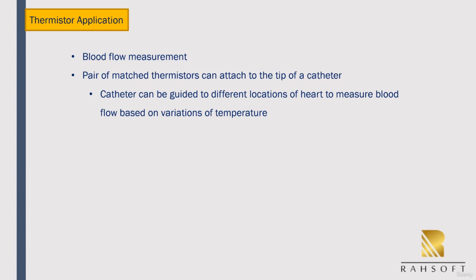They can be heated by a coil or flushed with cold saline to measure blood flow rates. When flushed with cold saline, the first sensor gets cooled more than the second because the blood flow warms up the saline that reaches the second sensor.